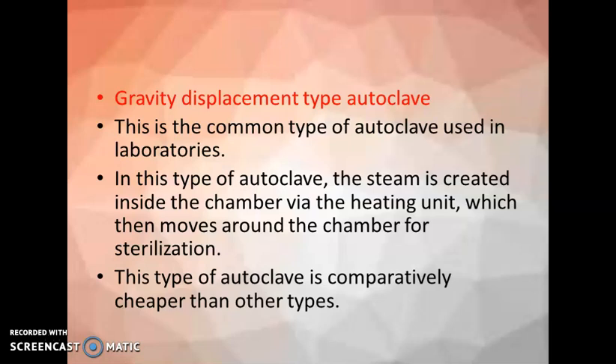The next type of autoclave is the gravity displacement type autoclave. This is the commonest type of autoclave used in laboratories. In this type of autoclave, steam is created inside the chamber through the heating unit, which then moves around the chamber for sterilization. This type of autoclave is comparatively cheaper than other types.